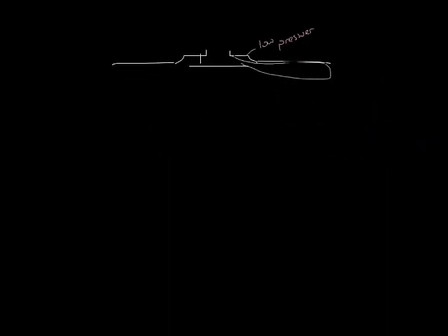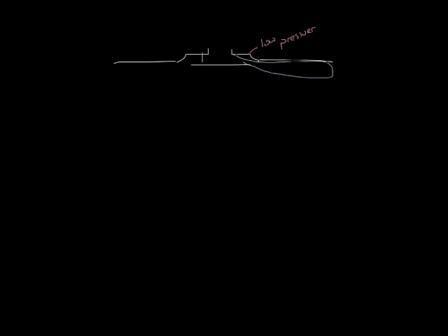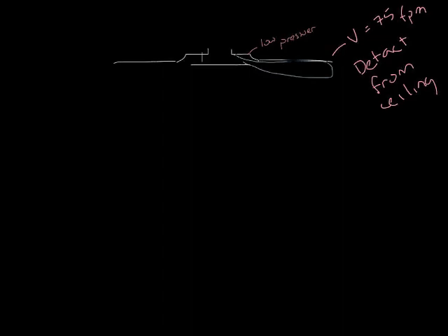Let's make a little more room here. Okay, so at this point, the weight of the air, we're assuming it's in cooling, will overcome the momentum and you'll lose the surface effect. At this point, the airflow will detach from the ceiling. Once it detaches from the ceiling, it'll start to slow down quickly, and so T50 will be shorter than the isothermal catalog data. This is unless it runs into a wall or another diffuser's airflow. So let's look at what happens then.